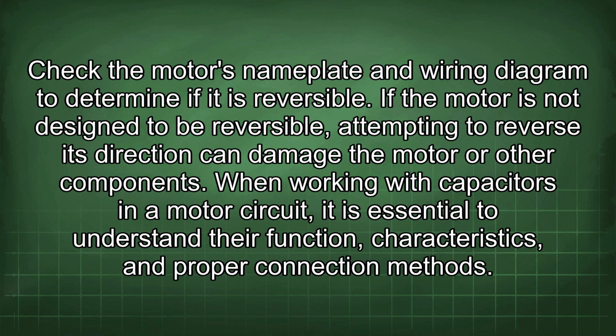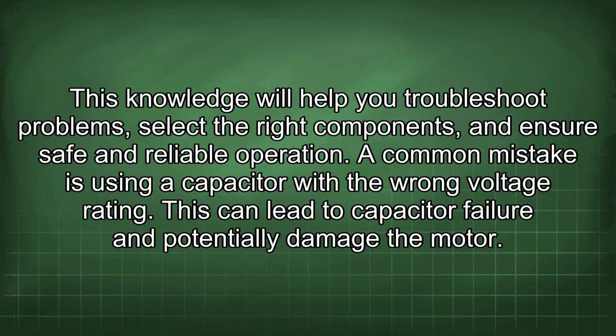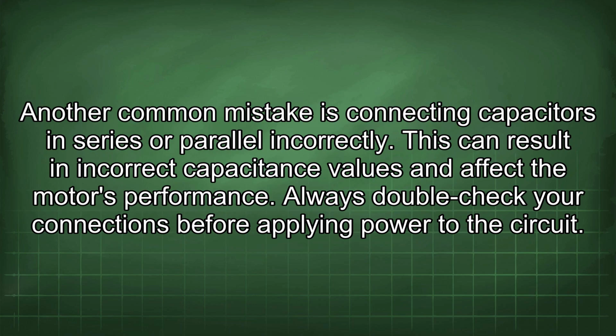components. When working with capacitors in a motor circuit, it is essential to understand their function, characteristics, and proper connection methods. This knowledge will help you troubleshoot problems, select the right components, and ensure safe and reliable operation. A common mistake is using a capacitor with the wrong voltage rating. This can lead to capacitor failure and potentially damage the motor. Another common mistake is connecting capacitors in series or parallel incorrectly. This can result in incorrect capacitance values and affect the motor's performance. Always double-check your connections before applying power to the circuit.